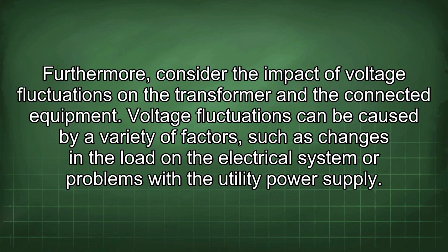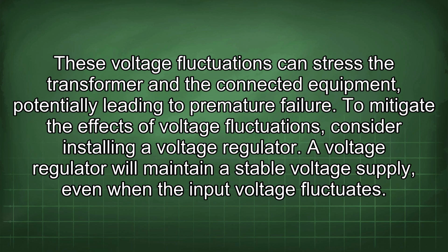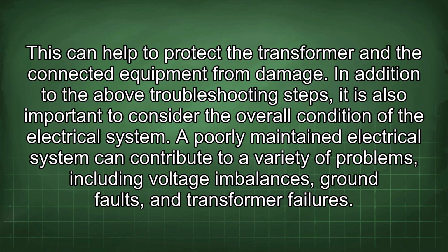Furthermore, consider the impact of voltage fluctuations on the transformer and the connected equipment. Voltage fluctuations can be caused by a variety of factors, such as changes in the load on the electrical system or problems with the utility power supply. These voltage fluctuations can stress the transformer and the connected equipment, potentially leading to premature failure. To mitigate the effects of voltage fluctuations, consider installing a voltage regulator. A voltage regulator will maintain a stable voltage supply, even when the input voltage fluctuates. This can help to protect the transformer and the connected equipment from damage.